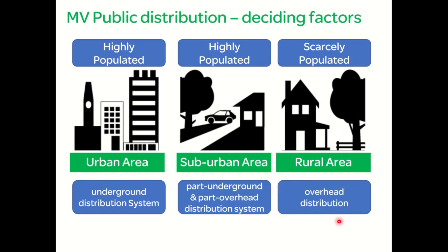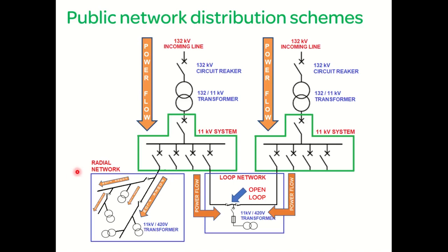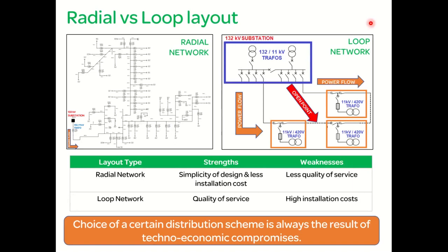Distribution schemes in the public network are typically of two types: radial network and loop network. In a radial network, there is a single feeding line from the MV switchgear in the high voltage substation, and power is distributed like branches in a tree — any fault in the line can cause a blackout in the entire area. In the loop network, power is distributed using two sources from the MV switchgear; however, at one time only one loop remains closed and the other remains open, so in the case of a power outage from one source, power supply is shifted to the other source. Examples of radial and loop networks show the single-source branch structure versus the two-source loop scheme.